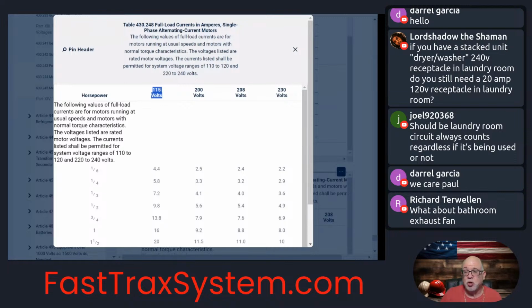Now don't get confused if it's for something like that dishwasher. That dishwasher, if it had said 10 amps times 115, then you use the 115. You use whatever they give you, okay? In our case, it was 120. But if you get a motor question and they give you 120 or they give you 115, you use the 115 column. Since the motor was a 120, we know that most motors on the nameplate might say 120, but they're rated at 115. So that's why we're using the 115 column, in case anybody ever got confused on that.